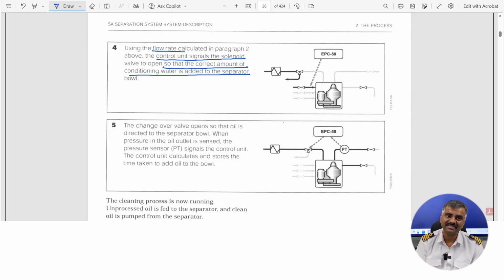When the conditioning water has gone in, this is just like a sealing water for the initial stage. So why is it called conditioning water? Conditioning is the term given for any sludge or impurities which remain, it becomes easier to desludge. If any sludge or something is remaining or stuck in the bowl, the conditioning water is actually conditioning this sludge. So that is why it is called conditioning water. Okay, now this recirculation, you can see in this diagram, until the conditioning water is going inside, EPC 50 has given the signal that as per the previous reference value we have to supply the conditioning water inside the bowl.